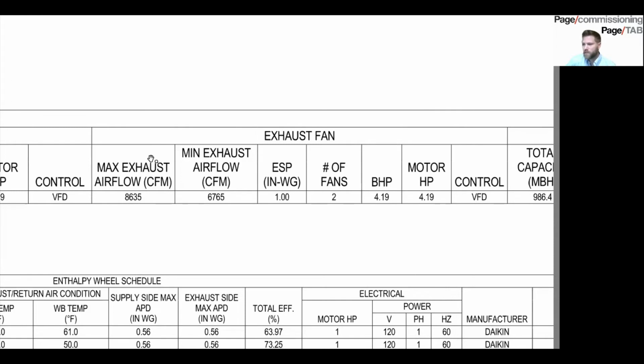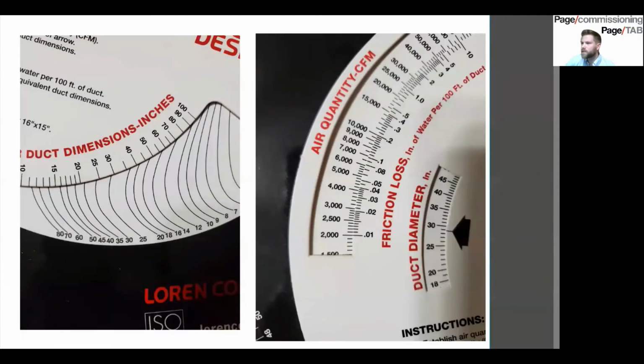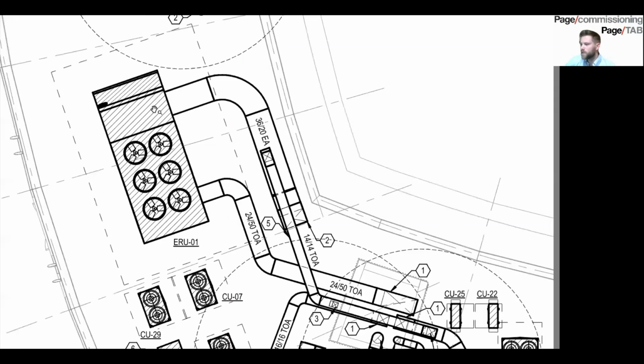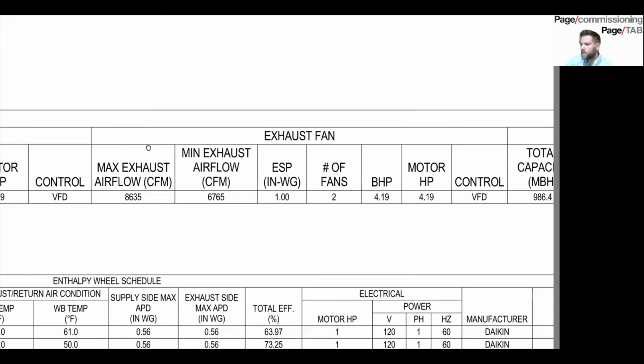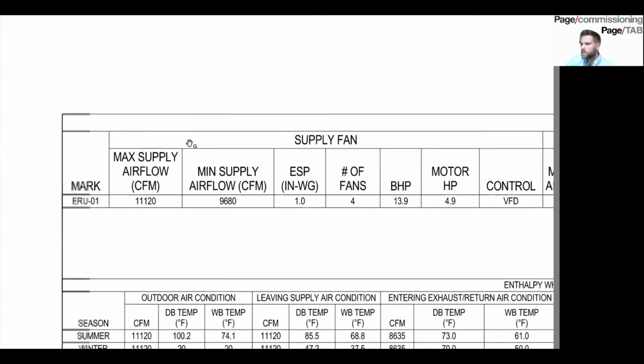And so that's a question to the engineer, or you log it in your issues log and send it to the engineer. Okay, now let's look at the outside air run. So your outside air is a 24 by 50. So if we go to the schedule and see what they want to get through that 24 by 50. So we're going to our supply fan. You got a max supply airflow of 11,000 roughly CFM.